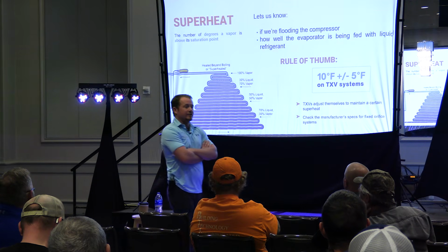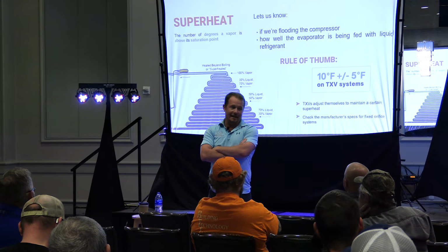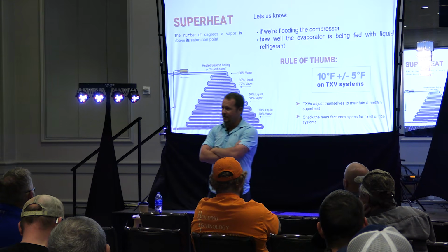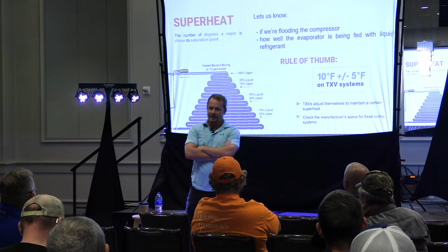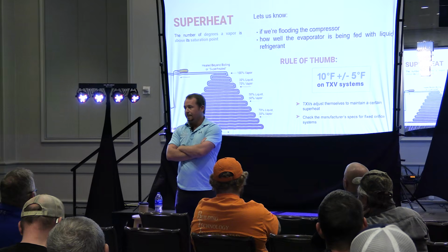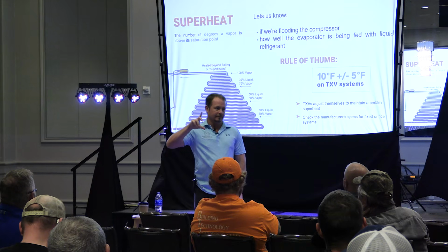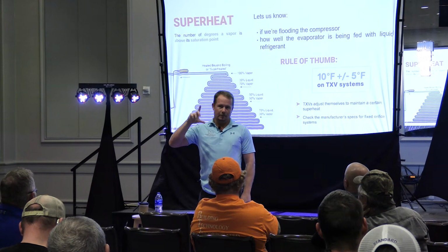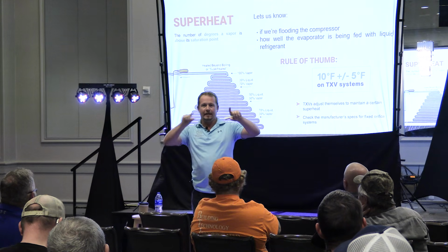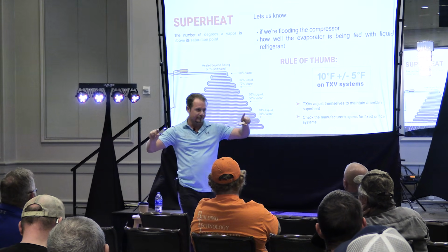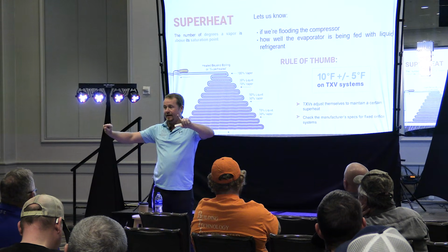So he's one of these guys who'll just put something out there, and he'll let you just dangle. You know, he's got the answer, kind of like I'm doing right now. He's got the answer, but he's just going to let you dangle, and he's going to let you say the wrong thing and look stupid, and then he'll tell you otherwise. What he pointed out to me is that if you have excessive subcooling, like massive subcooling, where somebody kept putting charge in it or whatever, and you have a pressure drop, it can actually eat up that subcooling before it gets to actually flash gas.